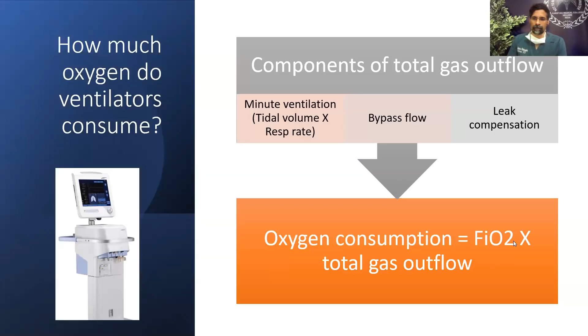As an example, if the minute ventilation of a patient on a ventilator is 10 liters per minute, and the leak volume, this number we can usually find as the ventilator monitors and displays it as well, is about 2 liters, and if this ventilator has a base flow of 6 liters per minute, then the total flow is 10 plus 2 plus 6. And if the fraction of inspired oxygen is 0.6, for example, then the total oxygen consumption per minute comes to about 10.8 liters per minute. That is about 650 liters per hour.